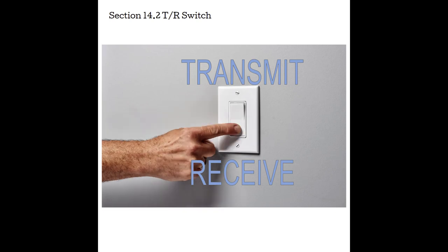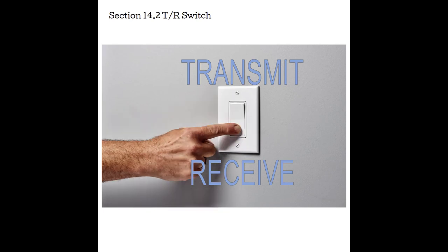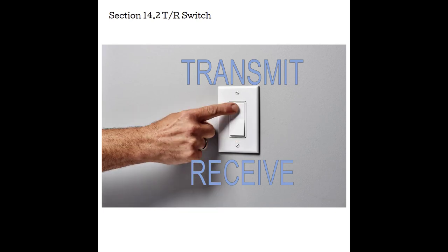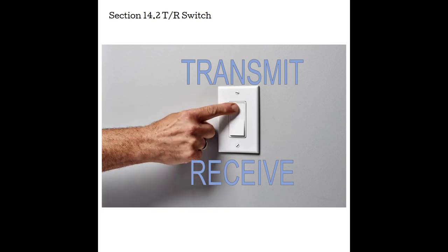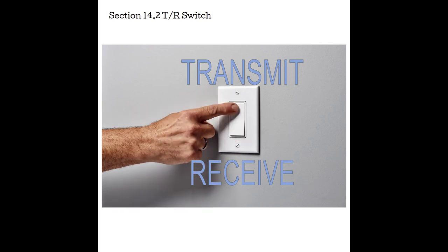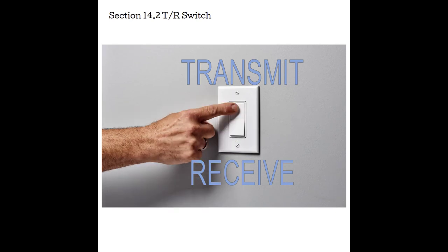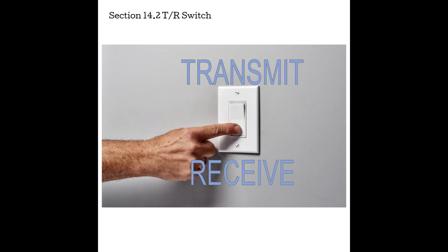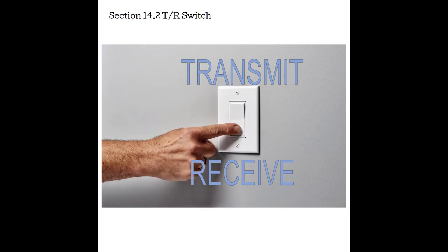When the machine is in transmit mode, the strong voltages really need to be sent to the transducer. If they were to somehow get misdirected into the machine components, it could actually really fry our system. So the TR switch has the responsibility to make sure that those really strong voltages are going to the transducer during transmission.